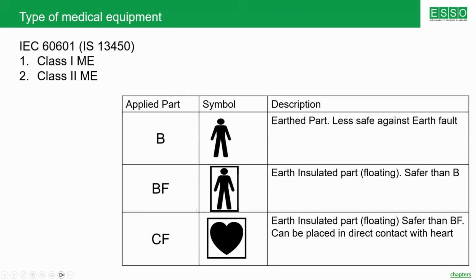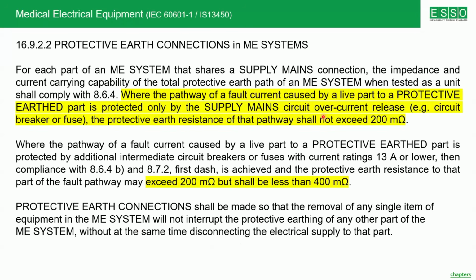Applied parts means the parts of these electrical biomedical equipment which are touching the body of the patient. The requirements of earthing for this biomedical equipment are explained in various clauses of IEC 60601. Example, clause 16.9.2.2, protective earth connection in a medical electrical system. I have highlighted some of the points where the pathway of fault current caused by a live part to a protective earth part is protected only by the supply mains circuit overcurrent release. The protective earth resistance of that pathway shall not exceed 200 milliohm.